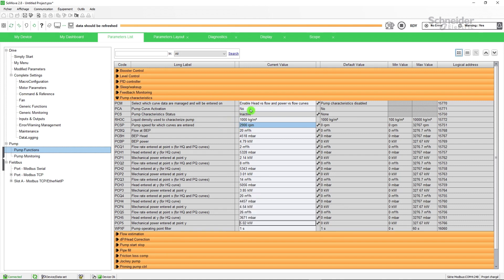To activate the curve, pump curve activation must be set to yes. Then check the pump characteristics status. If active is displayed, the data are consistent and are locked. If failed is displayed, that means some points have not been entered or data entered doesn't respect the rules.